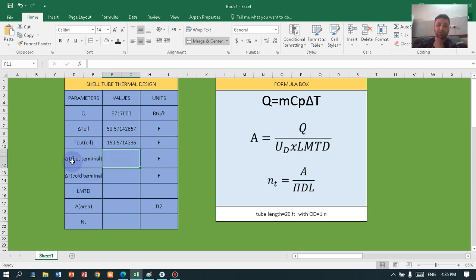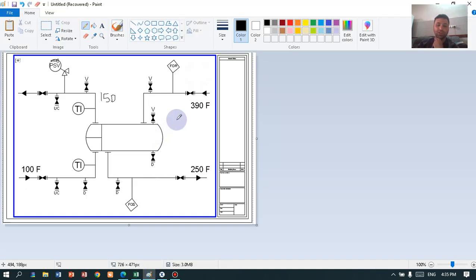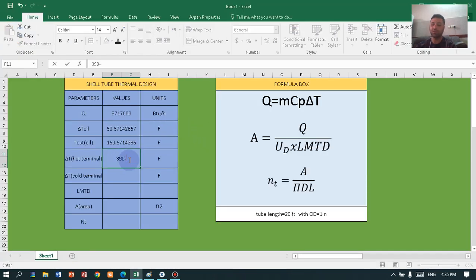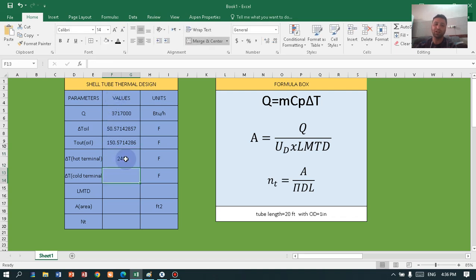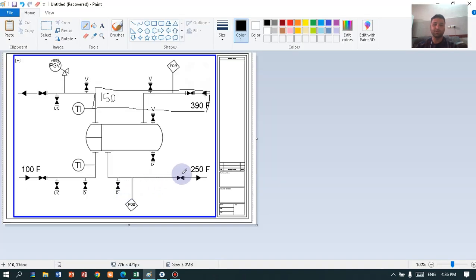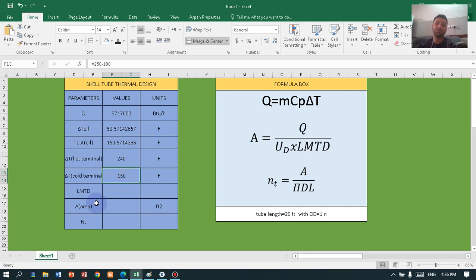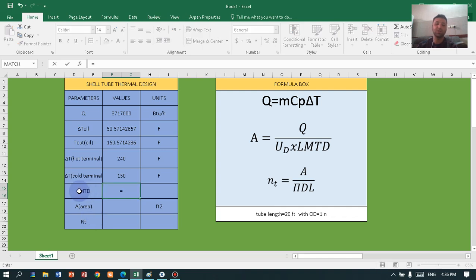For calculating the differential temperature at the hot terminal and cold terminal, I have drawn the shell and tube diagram here. The hot terminal has 390 and 150, which we calculated — insert 390 minus 150. Make sure you have inserted the equal sign so Excel calculates the differential temperature. Then press equal for the cold terminal: we have 250 and 100 — insert this number as well, giving us the hot terminal and cold terminal values.